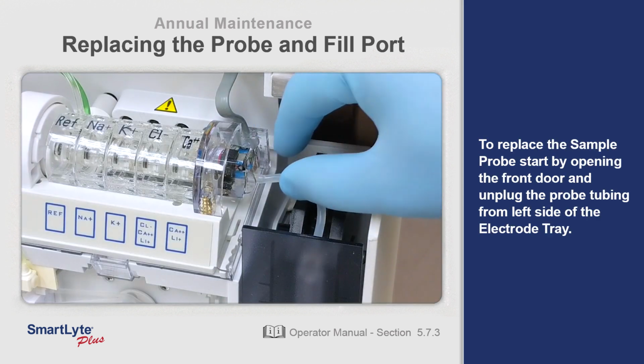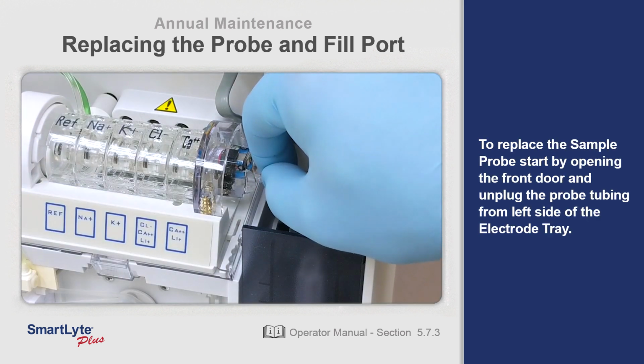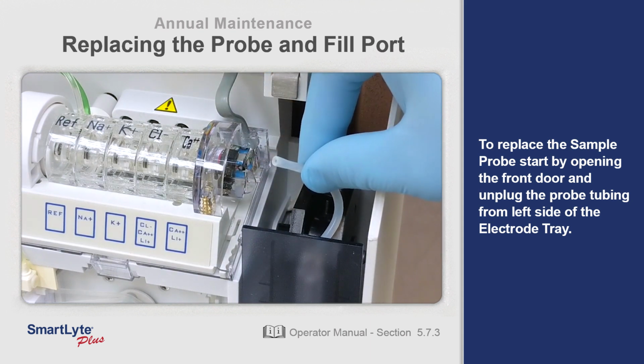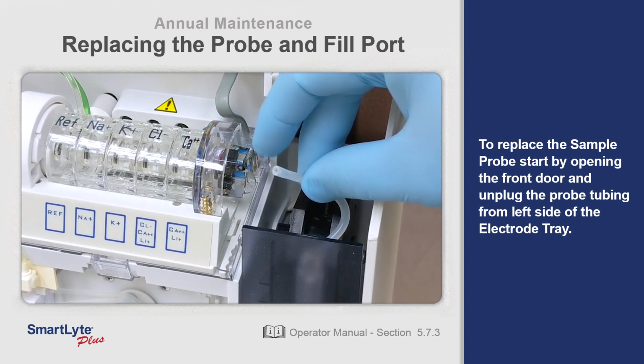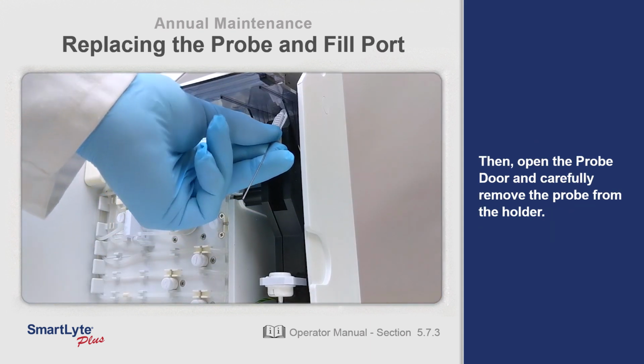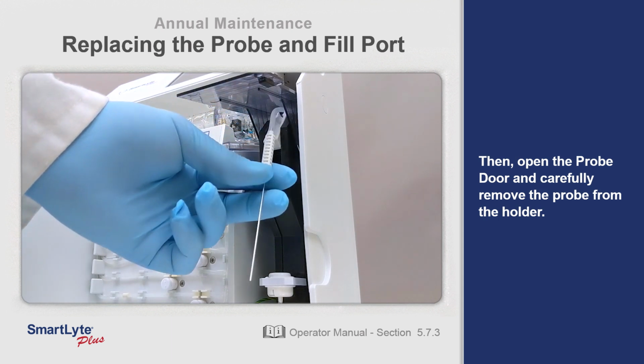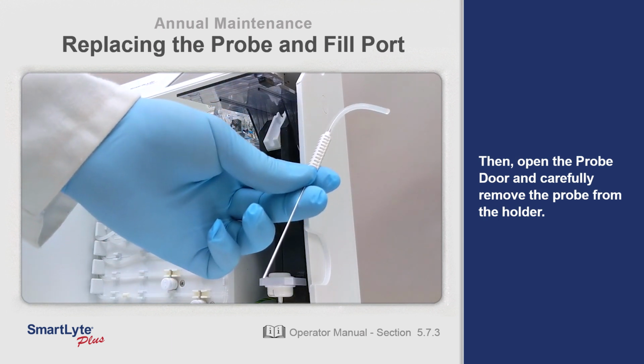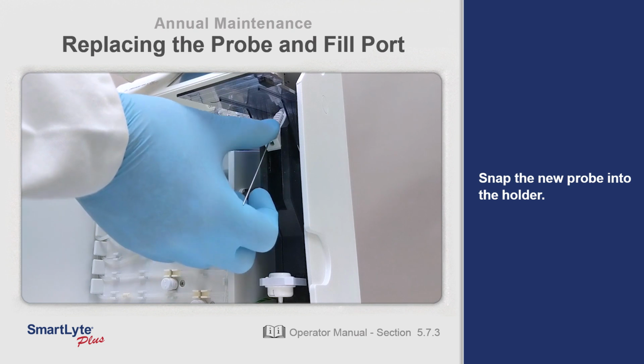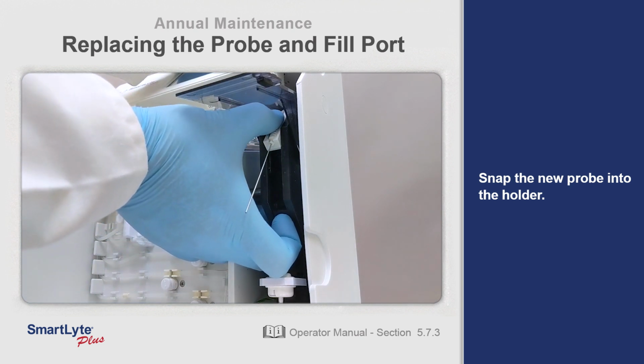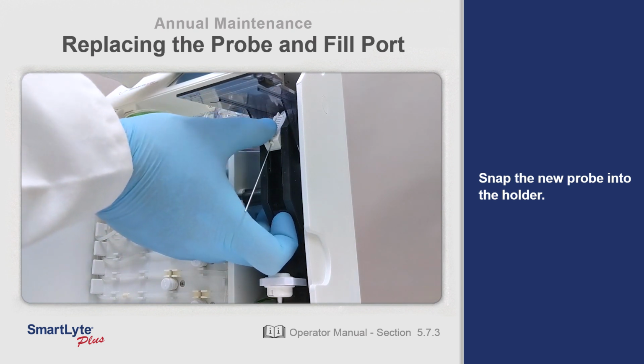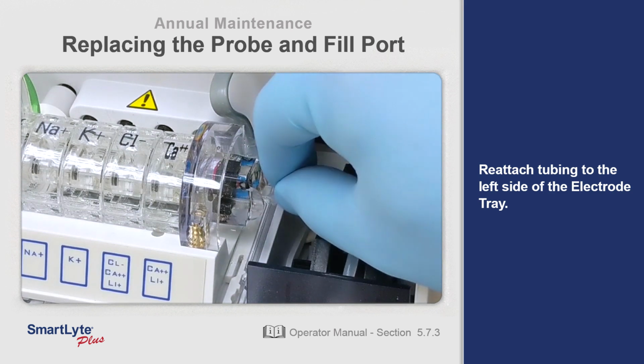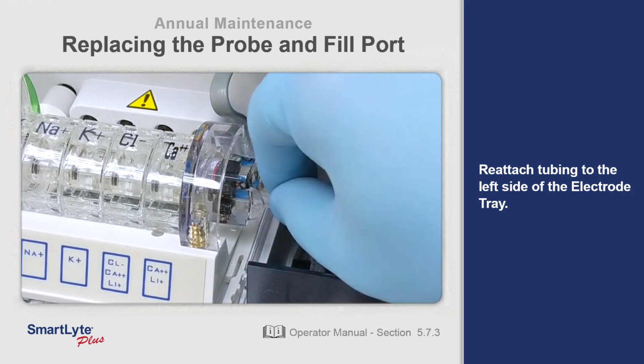To replace the sample probe, start by opening the front door and unplug the probe tubing from the left side of the electrode tray. Then, open the probe door and carefully remove the probe from the holder. Snap the new probe into the holder. Reattach the tubing to the left side of the electrode tray.